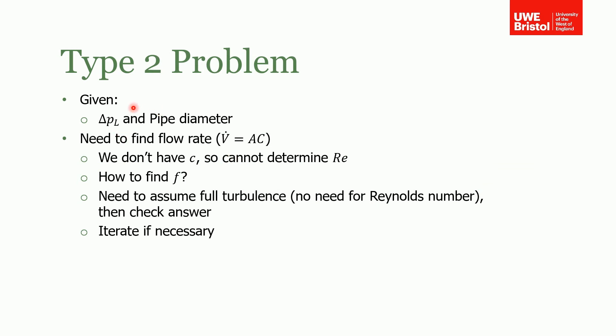The Type 2 problem is a little more complicated. If we know the pressure drop and the pipe diameter and we need to find the flow rate, the problem is that we don't know the velocity. If we don't know the velocity, we can't determine the Reynolds number, and if we can't determine the Reynolds number we can't find the friction factor. The way to do it is to assume full turbulence, because in the fully turbulent regime the friction factor is independent of the Reynolds number — it's only dependent on the relative pipe roughness. So you assume it's fully turbulent, calculate a friction factor, calculate the velocity, and iterate as necessary.